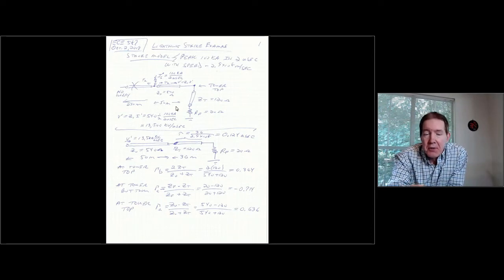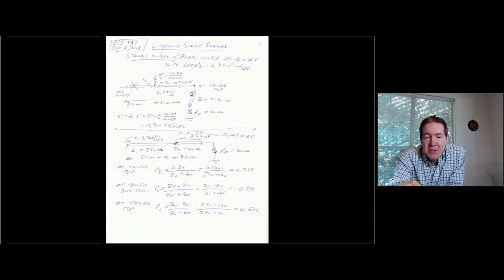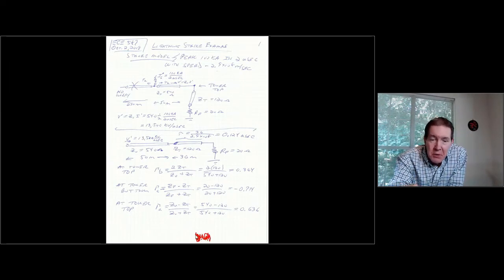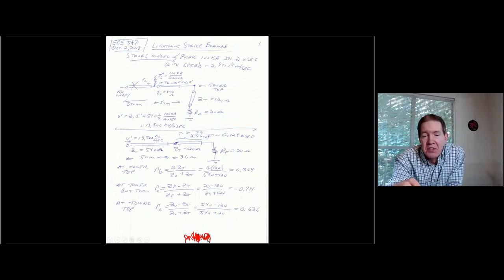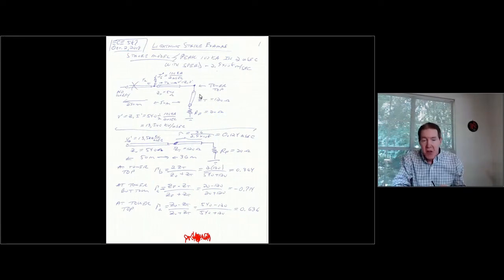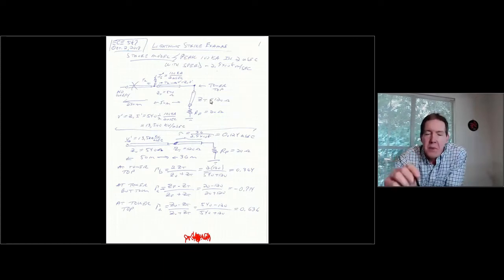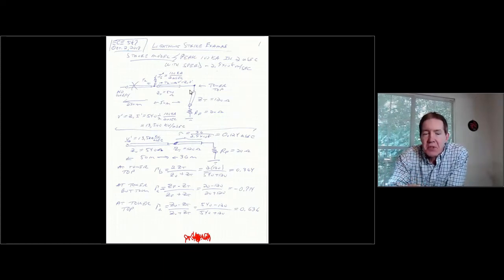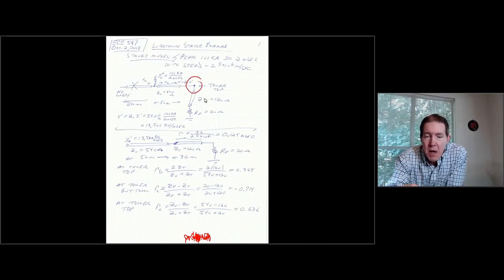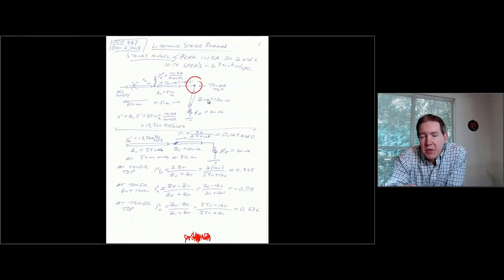The analysis actually begins when that surge hits the top of the tower. So when I'm doing this analysis, I'm setting my clock such that time equals zero corresponds to when the surge hits the top of the tower. Once it hits the tower top, it's going to travel down the tower, which has a surge impedance of 120 ohms.